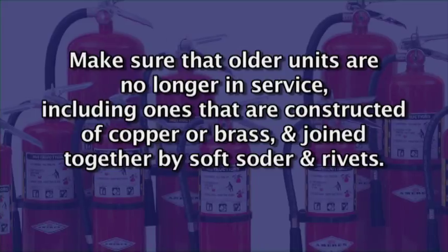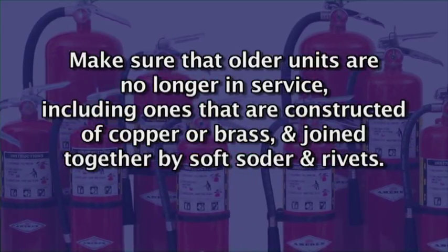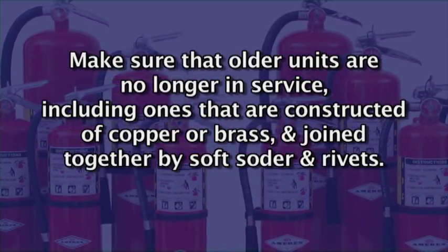One more quick point is to make sure that older, obsolete extinguishers are no longer in service. This includes units constructed of copper or brass and joined together by soft solder or rivets.